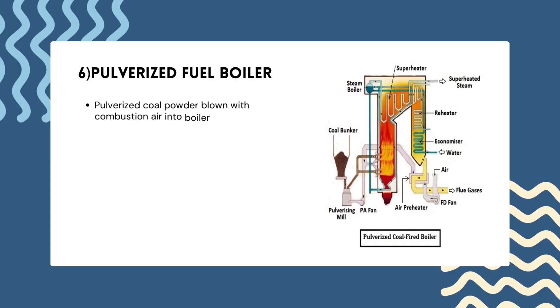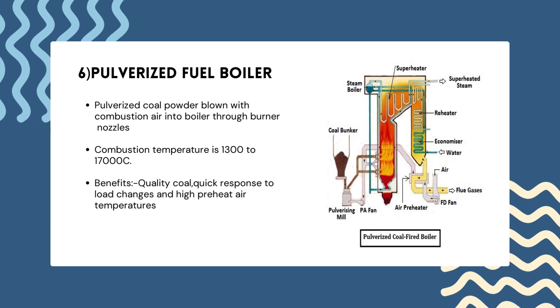In a pulverized fuel boiler, pulverized coal powder is blown with combustion air into the boiler through burner nozzles. Its combustion temperature is 1,300 to 1,700 degrees Celsius. These boilers are commonly used in large power plants due to their high efficiency and ability to generate large quantities of steam or electricity. Environmental regulations have led to development of cleaner technologies such as fluidized bed combustion and integrated gasification combined cycle (IGCC) systems.